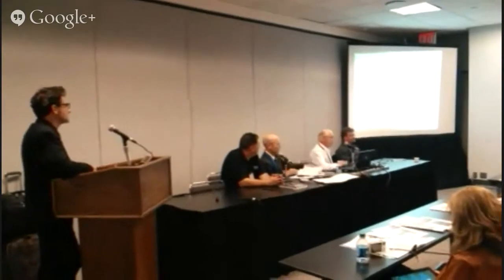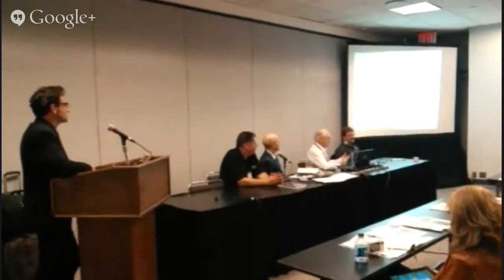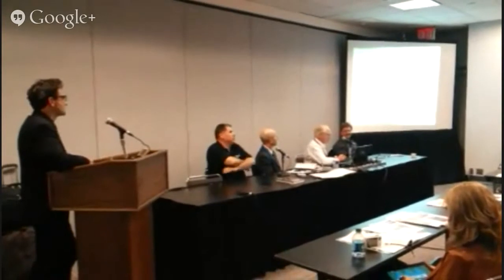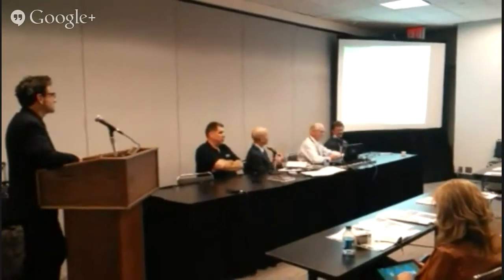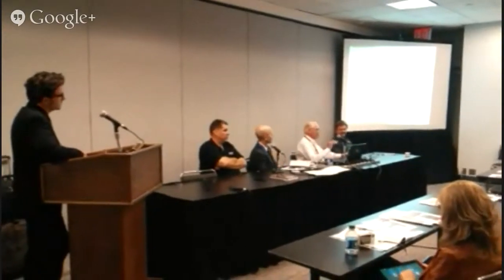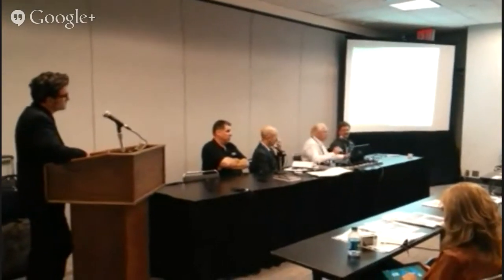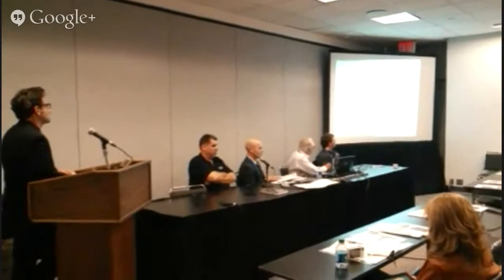And I've sat in on those meetings with the chiller guys, heat pump guys, VRF guys, so necessarily they want to make their stuff work, right? And AHRI is trying to come up with a fairly unbiased platform. The first thing that was done, which really makes sense, is that we're going to rate the equipment not just at 100%, but we're going to rate it at part load. And so AHRI decided that we would rate it at 4 points: 100, 75, 50, and 25% part load.